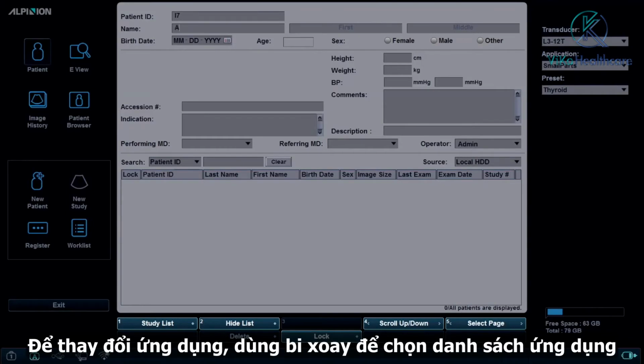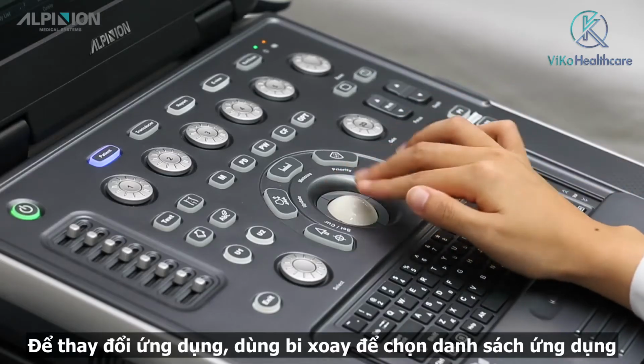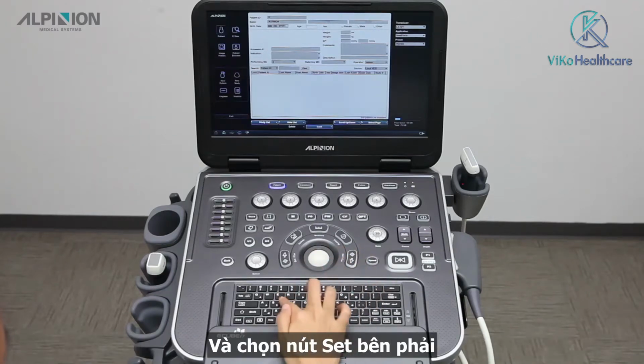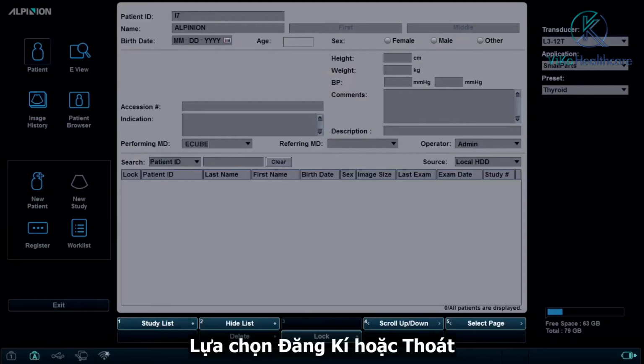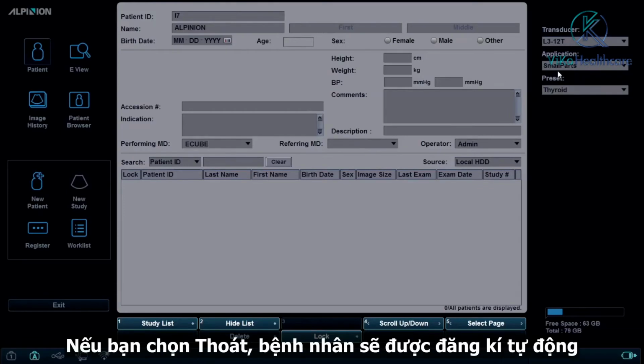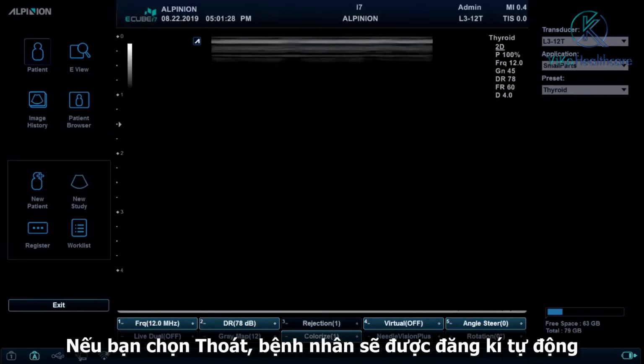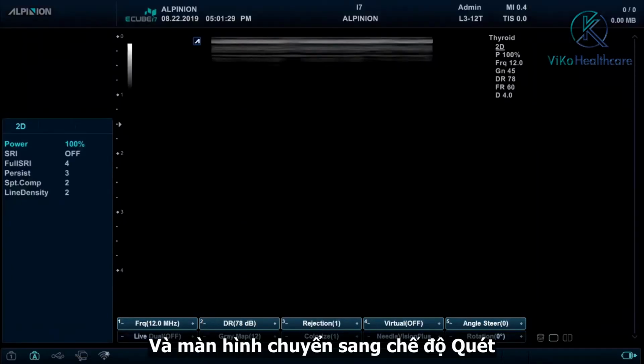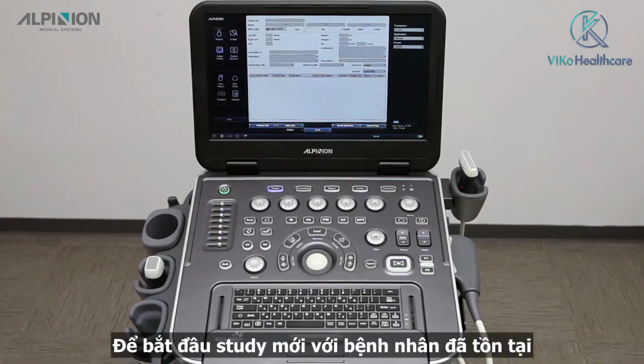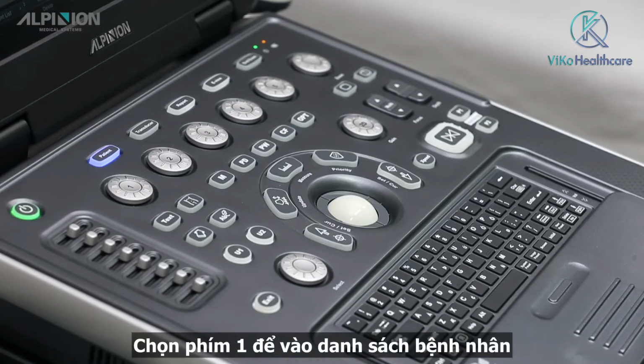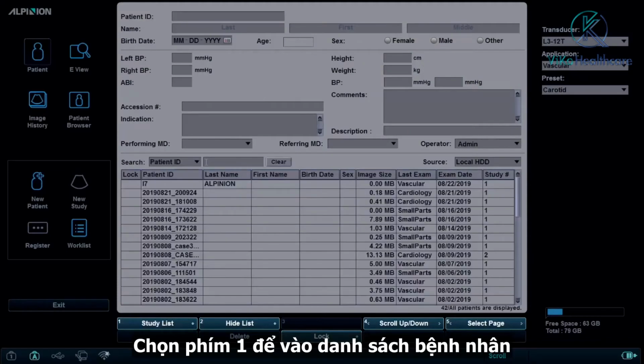To change application, use the trackball to select Application drop-down list and press right side Set key. Select Register or Exit. If you click Exit, patient will be registered automatically and screen turns to scan mode. To start a new study with an existing patient, press the soft key 1 to enter the patient list.